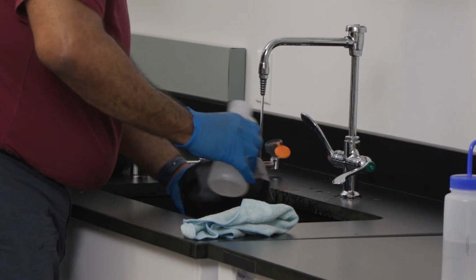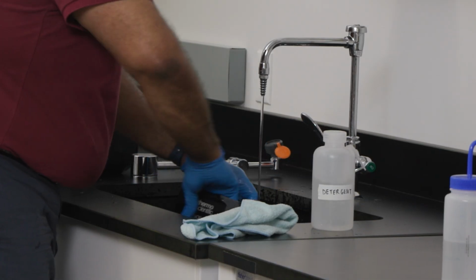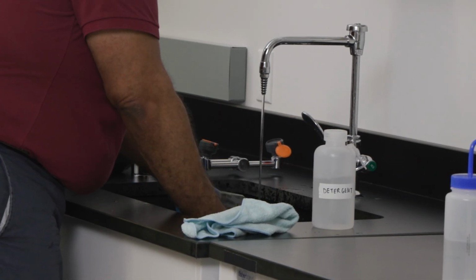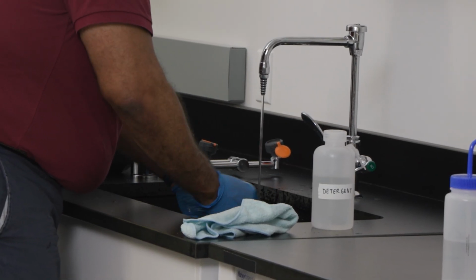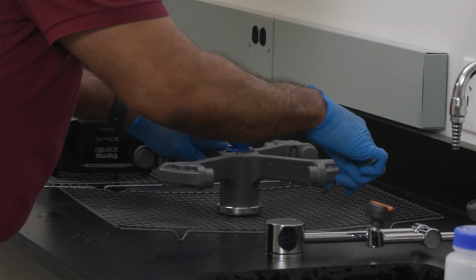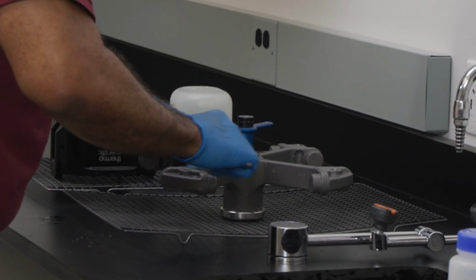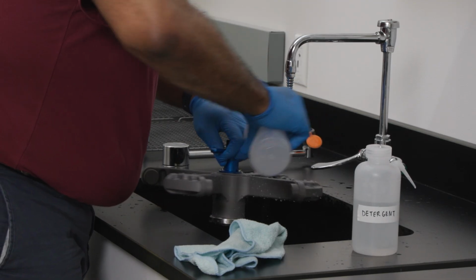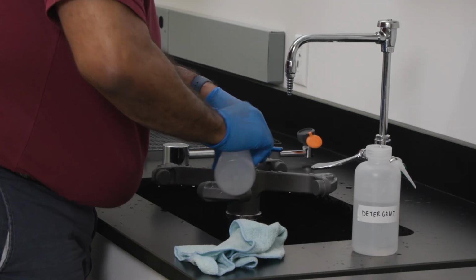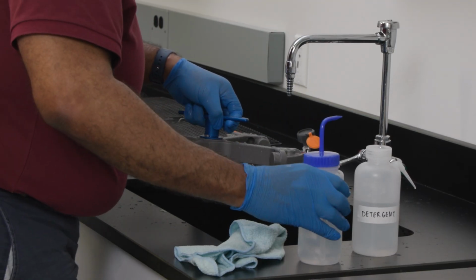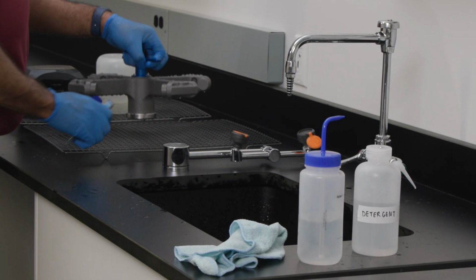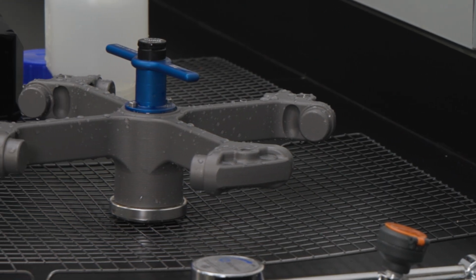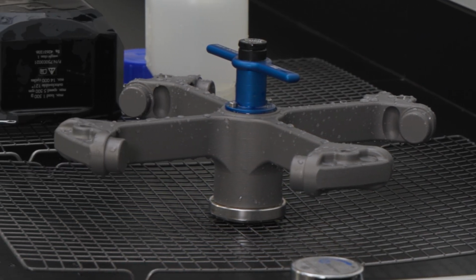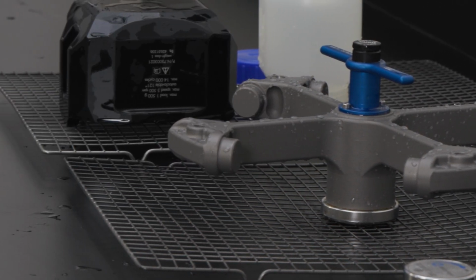Rinse the rotor and accessories with warm water and a suitable neutral detergent. Clean away the grease from the rotor trunnions. Then, use a soft brush without metal bristles to remove stubborn residue. Rinse rotor and accessories with distilled water. To drain, place the rotor on a plastic grate with the cavities pointing down. If natural airflow is insufficient, place the rotor on a ventilated shelf to avoid condensation.